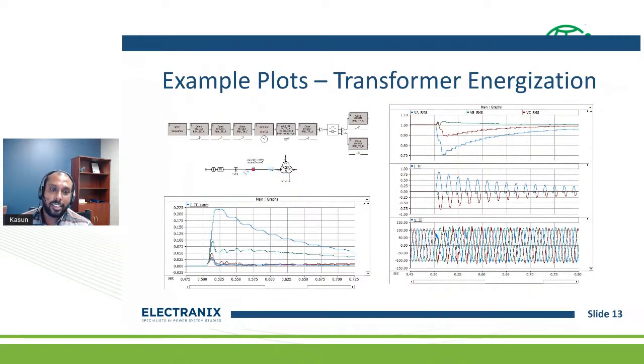This is one of the plots of a transformer energization study. When we energize a transformer, we know that we have inrush currents, and these inrush current magnitudes or the voltage dip at the connected bus are essential to see, especially if we have parallel transformers.